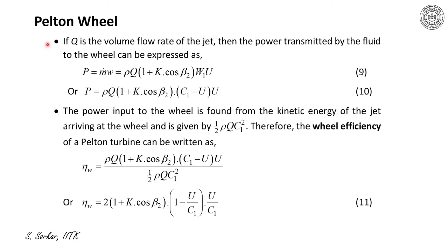If Q is the volume flow rate of the jet, then the power transmitted by the water to the wheel can be expressed as P is equal to m dot into w, that is equal to rho Q within the bracket 1 plus K into cos beta 2 into W1 into U, where W1 is equal to C1 minus U. Thus putting the value of W1, power transmitted by the fluid to the wheel can be expressed as rho Q within the bracket 1 plus K into cos beta 2 within the bracket C1 minus U into U.